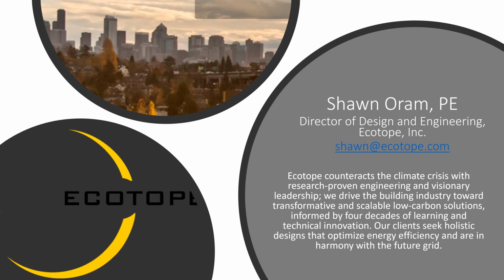That's a great point. I showed in this presentation that the skid we're developing ends up being about 120 watts per apartment if we're running 16 hours a day. A standard electric water heater is 4,500 watts. So the scale, or the electrical value of going central, is 4,500 watts per apartment becoming 120 watts. But we have seen in our work that transformers are a big piece of this. New construction is easy because you can get this stuff integrated; retrofit is a much different beast because you're stuck with what you've got.